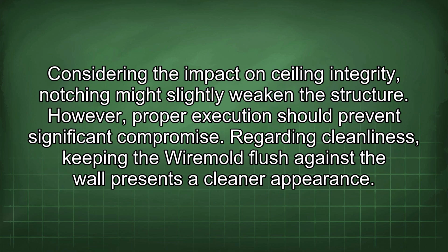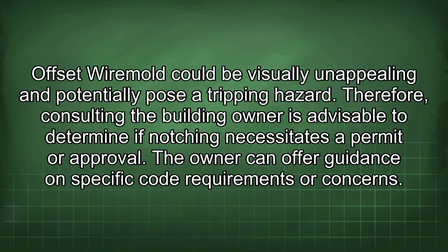Considering the impact on ceiling integrity, notching might slightly weaken the structure. However, proper execution should prevent significant compromise. Regarding cleanliness, keeping the Wiremold flush against the wall presents a cleaner appearance. Offset Wiremold could be visually unappealing and potentially pose a tripping hazard. Therefore, consulting the building owner is advisable to determine if notching necessitates a permit or approval. The owner can offer guidance on specific code requirements or concerns.